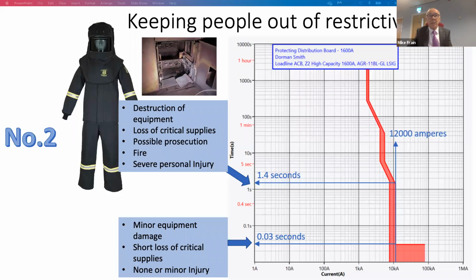It could be critical supplies, it could be in a hospital or something like that, possible prosecution, possible fire, and possible severe personal injury, or alternatively use a suit like that. But that doesn't stop the first four things there. Or if it trips in 30 milliseconds, we're talking about minor equipment damage, short loss of critical supplies, clean up, put it back, or none or minor injury at that point.